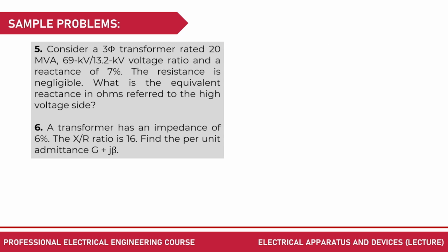Next is number 5. Consider a three-phase transformer rated 20 megavolt ampere, 69 kilovolts down to 13.2 kilovolt ratio, and a reactance of 7%. The resistance is negligible. What is the equivalent reactance in ohms referred to the high voltage side? When you say 7%, this is also the same as 0.07 per unit. It's the same thing.